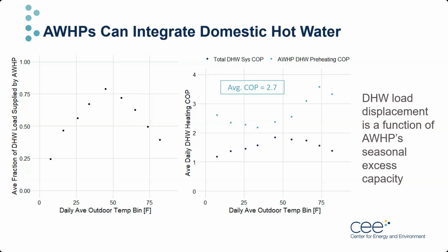Recall that this system only provides domestic hot water heating when it's not responding to space conditioning calls, so domestic hot water was always treated as a secondary priority. This explains the clear peak on the left-hand plot, as the ability for the system to provide water heating is the inverse of the combination of heating and cooling loads. So we get less water heating when it's really cold, and we also get less when it's really warm out. But for a good band in between, we can displace a sizable chunk of the domestic hot water load at this home with an abnormally large need for water heating, so it's sort of a special case. Next slide.